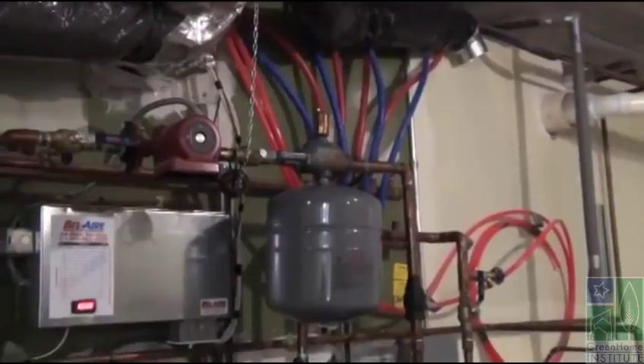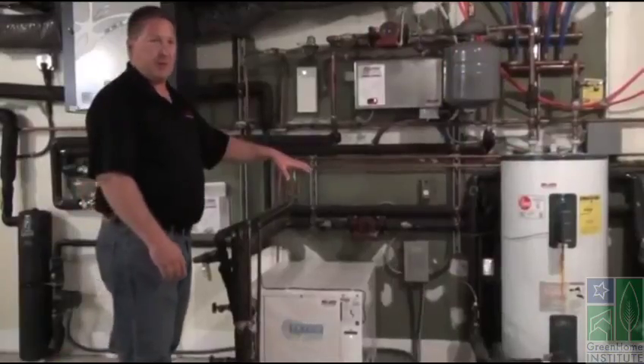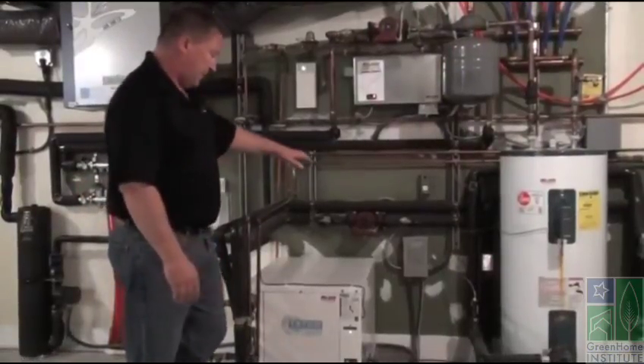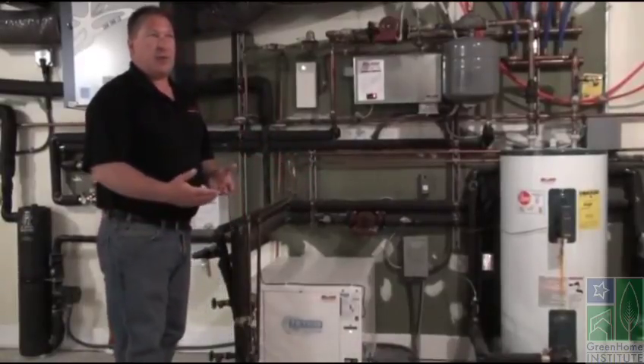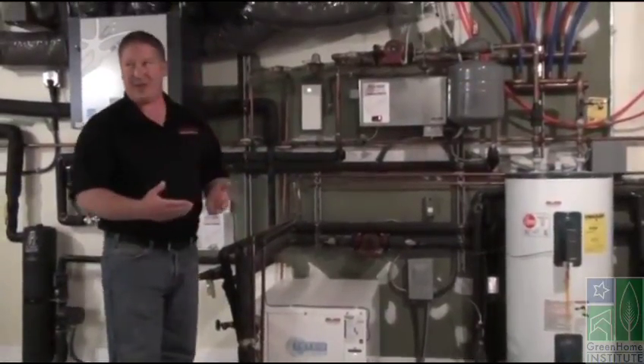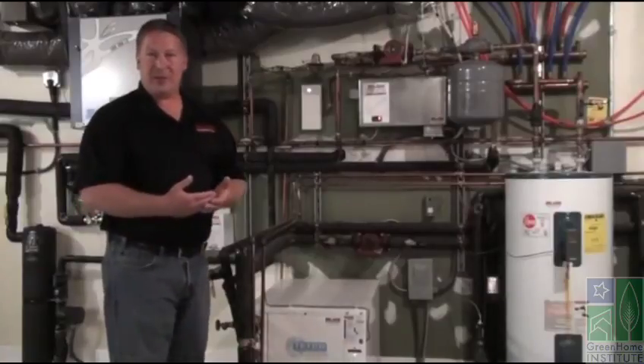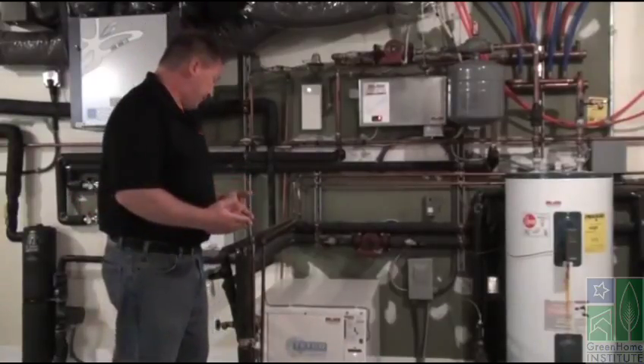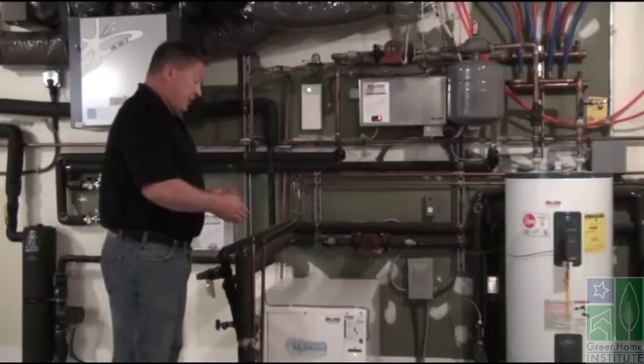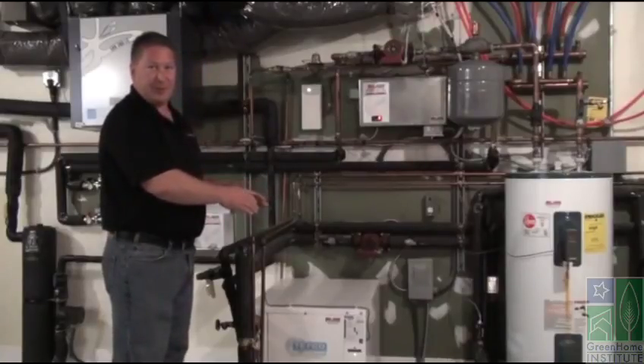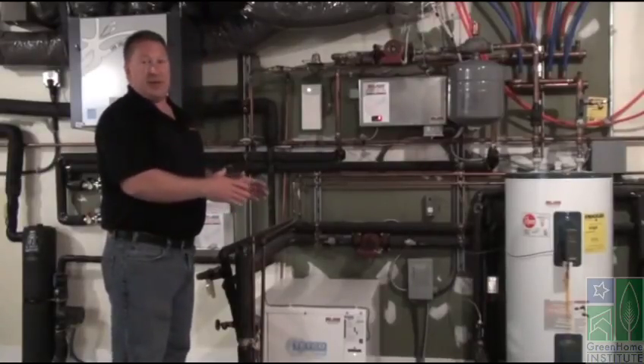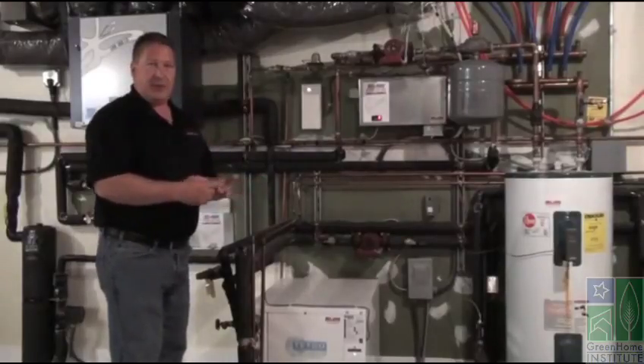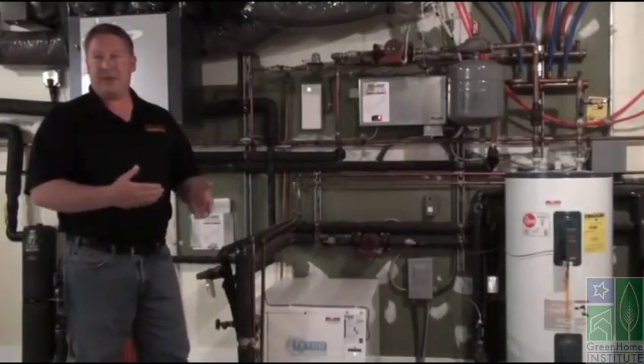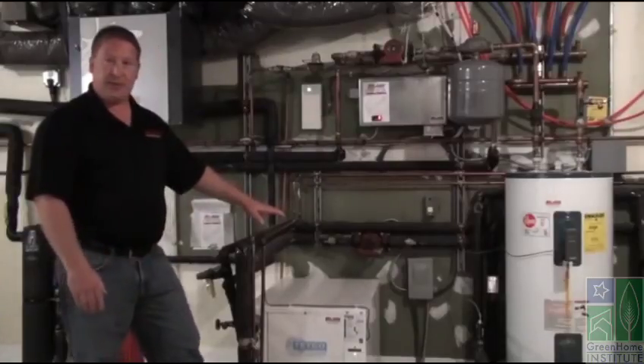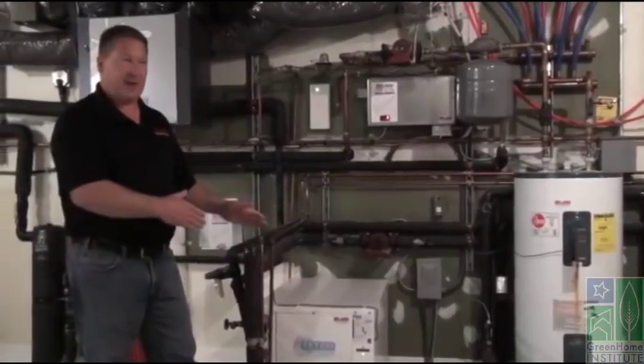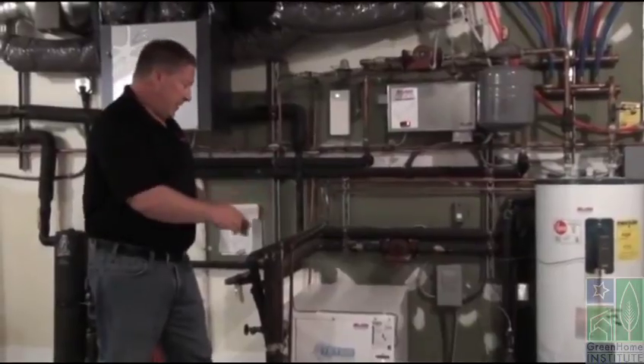The geothermal itself uses a compressor to do the work. It's a refrigerant compressor. It uses a refrigerant called R410A, which is an environmentally friendly refrigerant, which means that if it's actually released in the atmosphere, it's not going to deplete our ozone layer or cause any issues there. Maintenance on it is, it comes factory pre-charged and shipped pre-charged, so there's really nothing as installers or service technicians that we need to do with the compressor unless there's a failure. So we don't even like to hook our gauges to it when we first install them, because they've done that at the factory and made sure everything was good there.